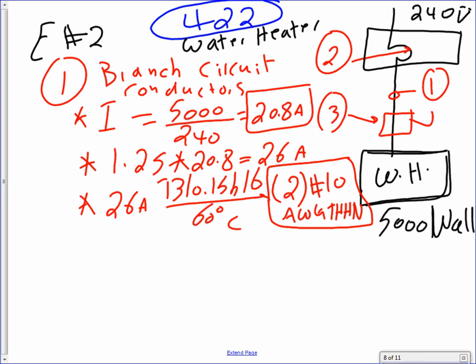Electric water heaters, storage water heaters. So we got that one. Branch circuit overcurrent protection shall not exceed the protective device rating marked on the appliance. All right, so we sized this one. The second one we need to size, guys, is the overcurrent protection.